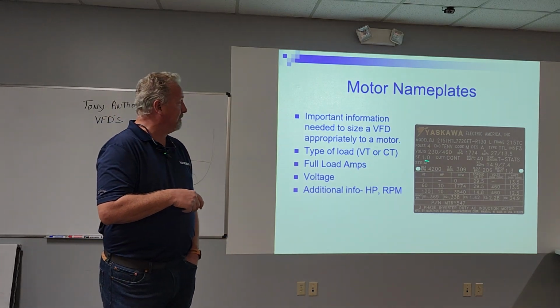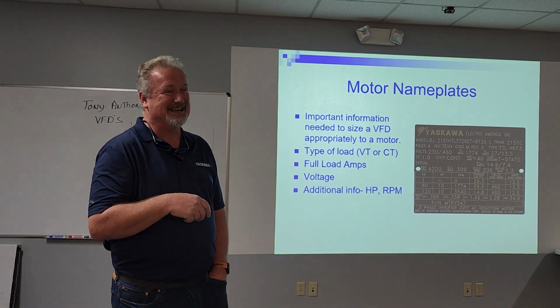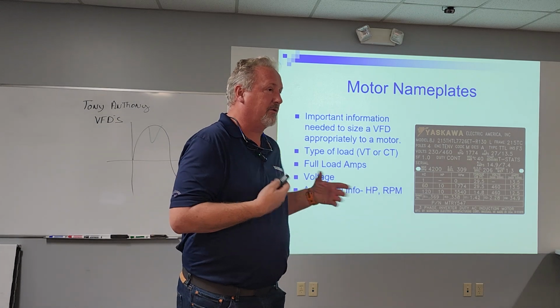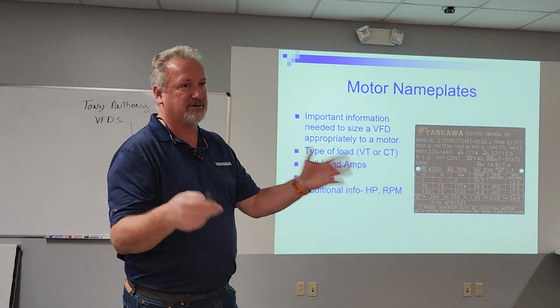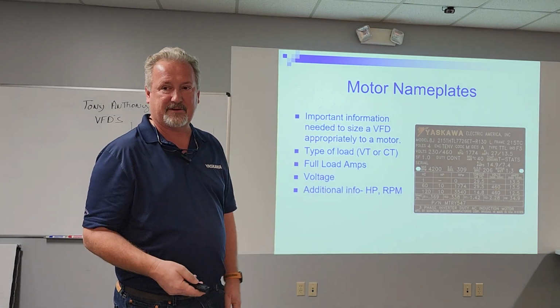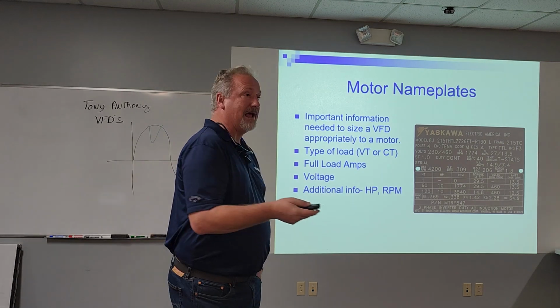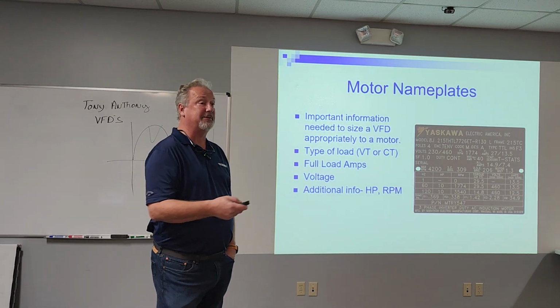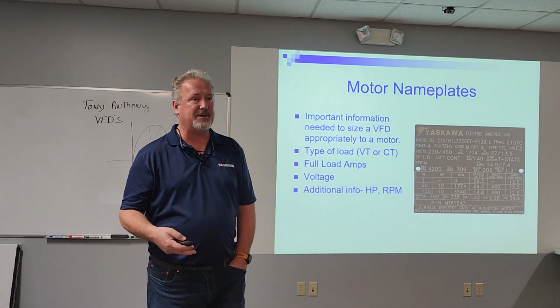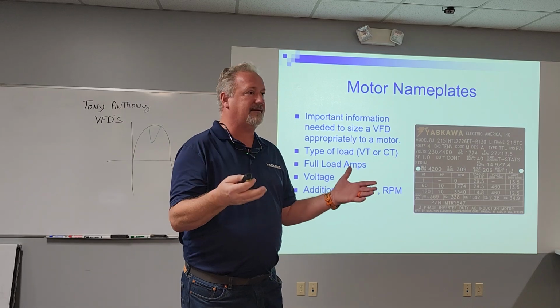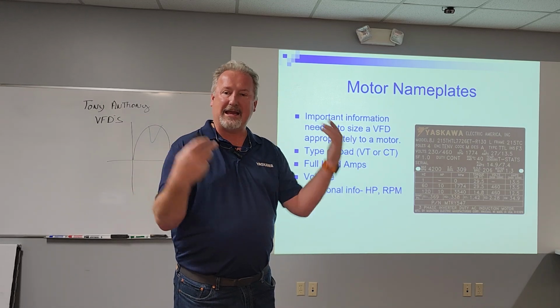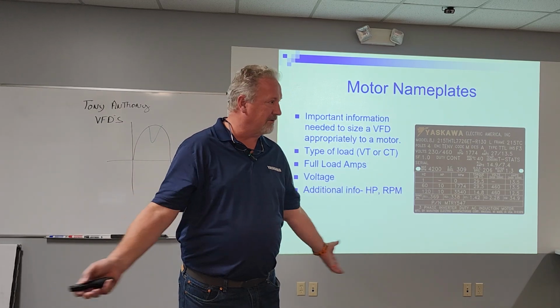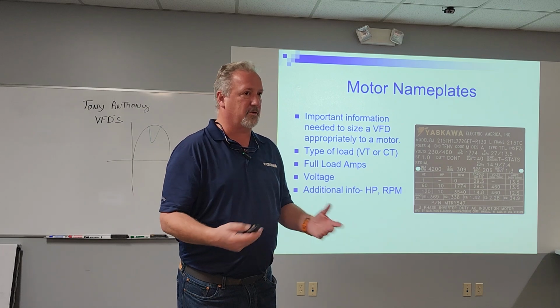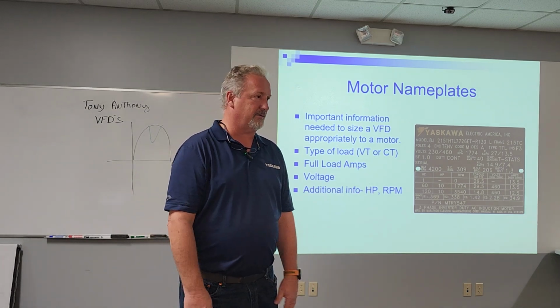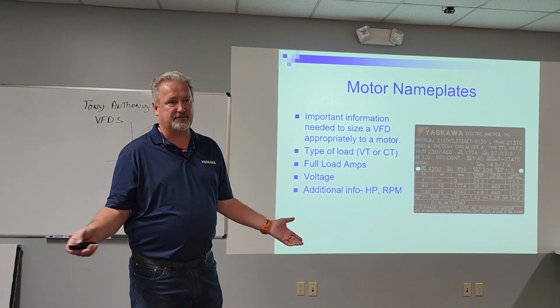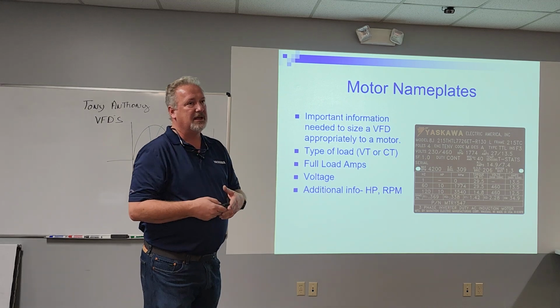No, but the voltage is... in the industrial world, we have to worry about constant torque or variable torque loads. You guys are dealing 99.9% of the time with variable torque loads. Full load amps is more important than horsepower, and the reason is every drive manufacturer out there sizes our drives based off of NEMA B 1800 RPM, the most common motor out there. So, 4-pole 1800 NEMA B motor. We all size our drives based off that.